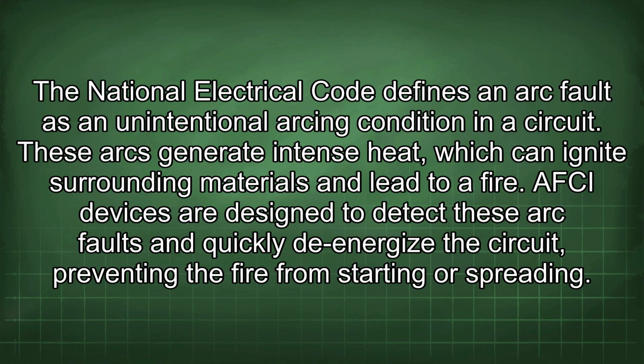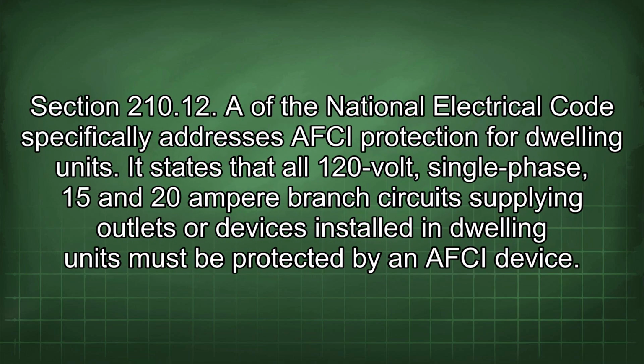The National Electrical Code defines an arc fault as an unintentional arcing condition in a circuit. These arcs generate intense heat, which can ignite surrounding materials and lead to a fire. AFCI devices are designed to detect these arc faults and quickly de-energize the circuit, preventing the fire from starting or spreading. Section 210.12 of the National Electrical Code specifically addresses AFCI protection for dwelling units. It states that all 120-volt, single-phase, 15 and 20-ampere branch circuits supplying outlets or devices installed in dwelling units must be protected by an AFCI device.